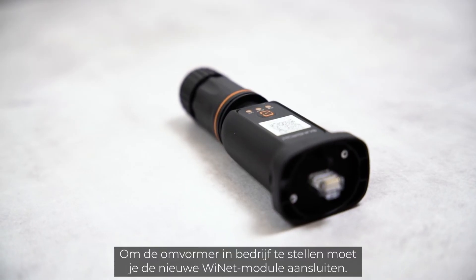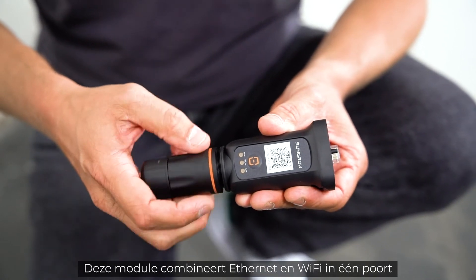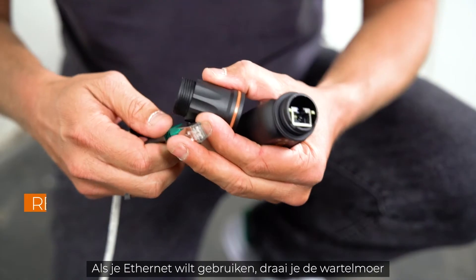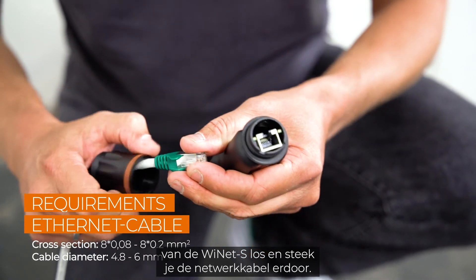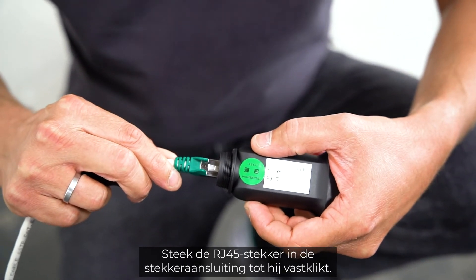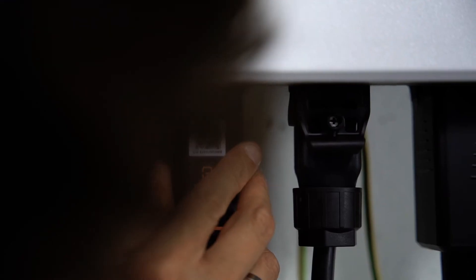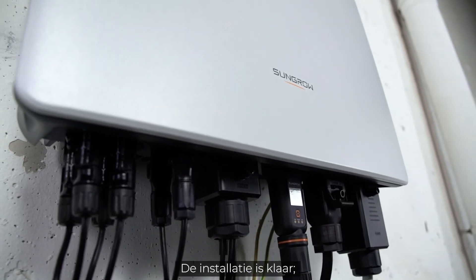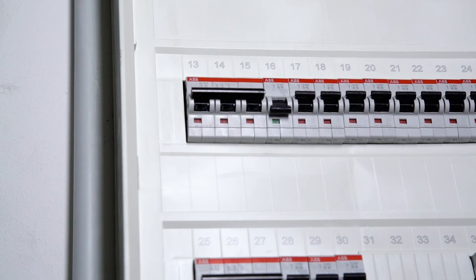For commissioning you have to connect the new WiNet module, which combines Ethernet and Wi-Fi in one port and is part of the delivery scope. If you want to use Ethernet, simply unscrew the swivel nut from the Ynet and thread the network cable through it. Insert the RJ45 plug into the plug connector until you hear a click, screw everything together, and plug the device in. If you want to use Wi-Fi, it's even easier — simply connect the module to the inverter. The installation is done.